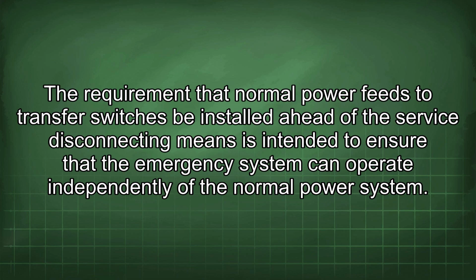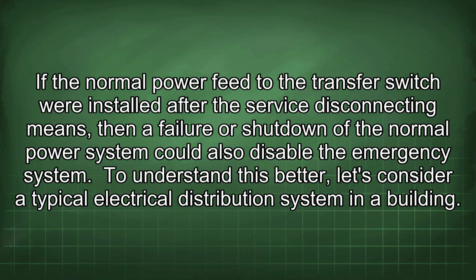The requirement that normal power feeds to transfer switches be installed ahead of the service disconnecting means is intended to ensure that the emergency system can operate independently of the normal power system. If the normal power feed to the transfer switch were installed after the service disconnecting means, then a failure or shutdown of the normal power system could also disable the emergency system.